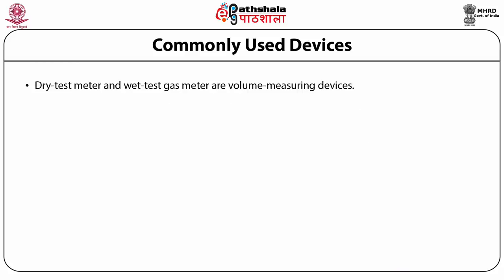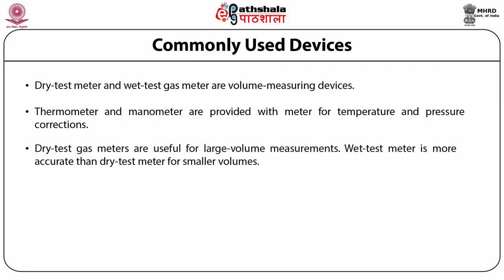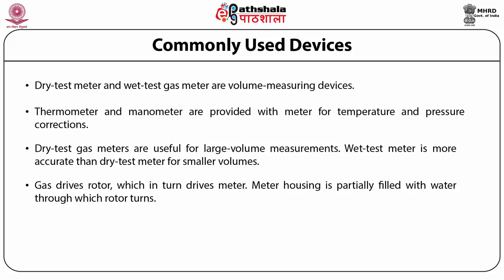The dry test meter and the wet test gas meter are volume measuring devices. In the dry test meter, a set of plastic bellows is alternately filled and emptied, thereby driving the dial pointer, while a system of valves requires very little pressure. A thermometer and manometer are provided for temperature and pressure correction. Dry test gas meters are useful for large volume measuring. The wet test meter is generally more accurate than the dry test meter for smaller volumes; the gas drives a rotor which in turn drives the meter, and the meter housing is partially filled with water through which the rotor turns.